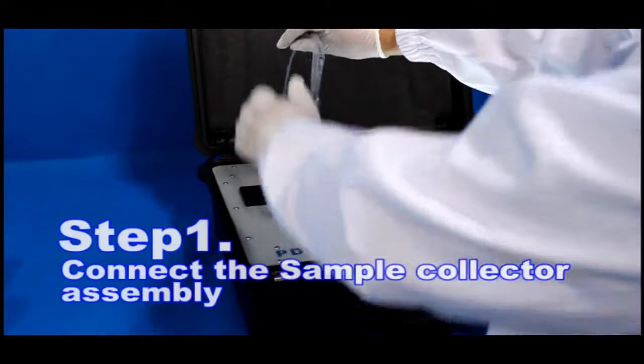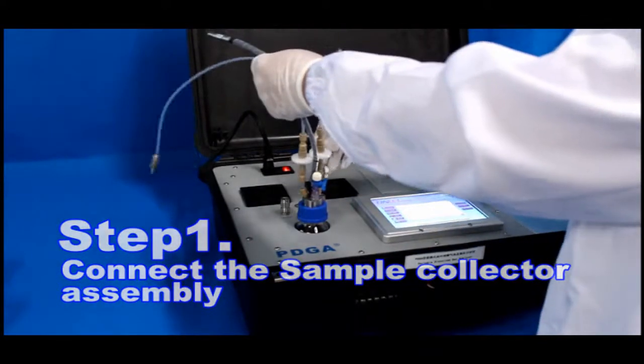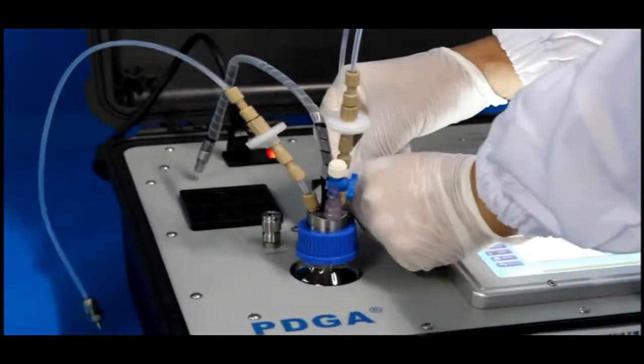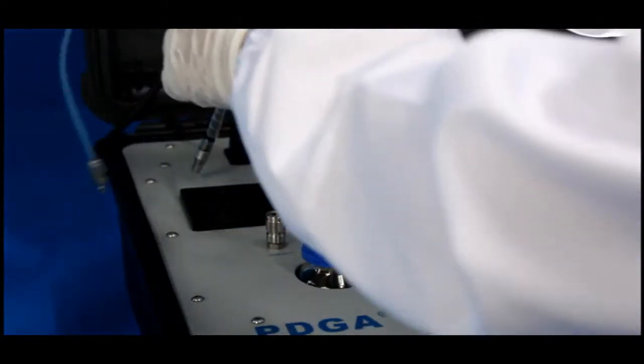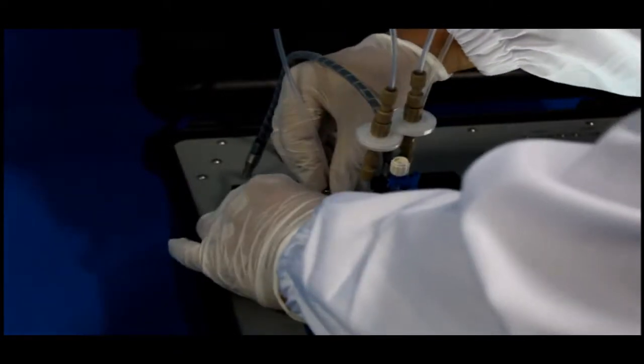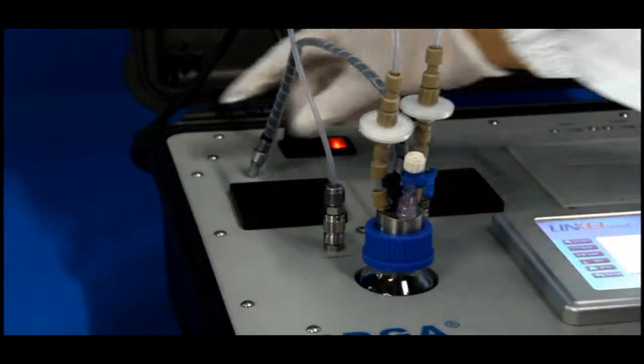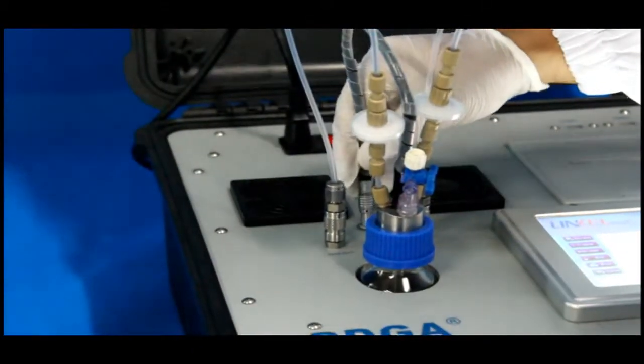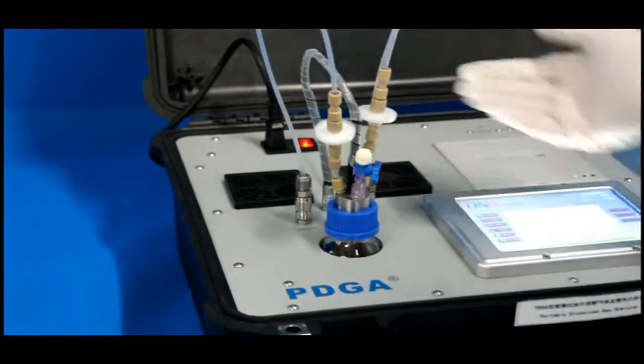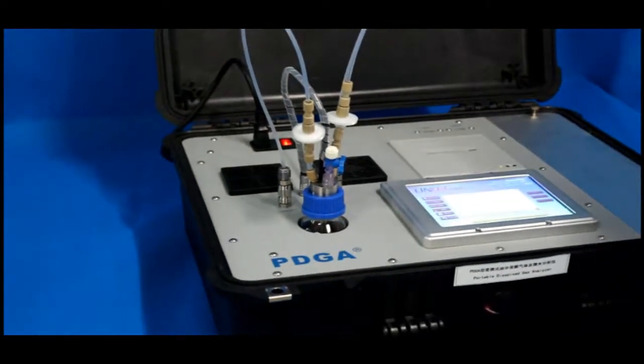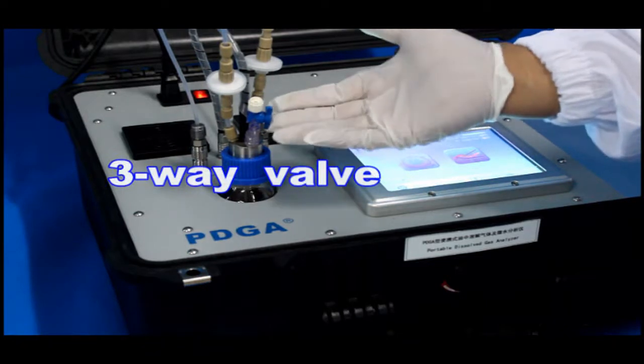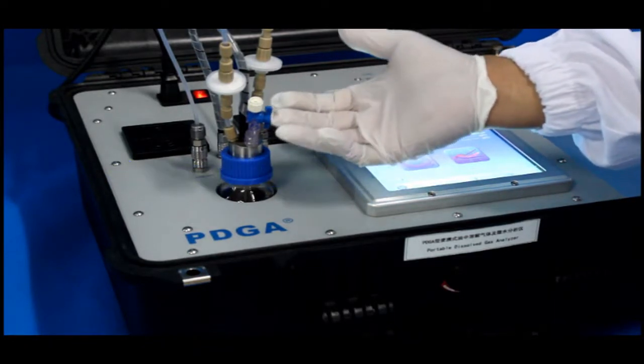Step 1. Connect the sample collector assembly to our PDGA instrument. 3-way valve allows you to inject oil into test bottle.